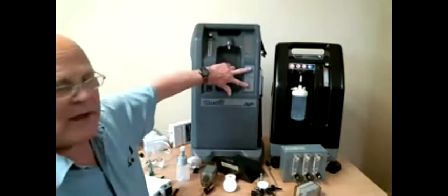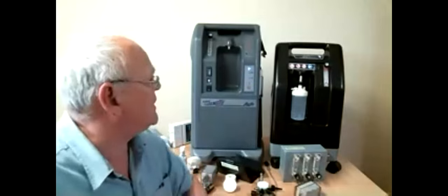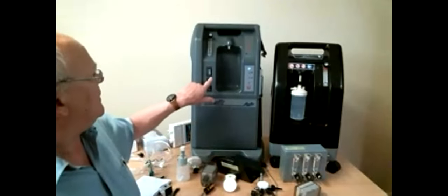So we have a range of alarms on here that will give you low oxygen, a maintenance alarm. If you over-demand for these two in particular, it will alarm and tell you you're trying to take too much oxygen from the concentrator. Lots of them do now put a red band on just to reinforce that you mustn't over-demand from them. If you do, you get a moisture buildup in the sieve beds, and that will destroy the machine. So it is extremely important not to over-demand from them. There's an hour counter on the front of this one. On this machine, it's on the back. So there are some variations between those.